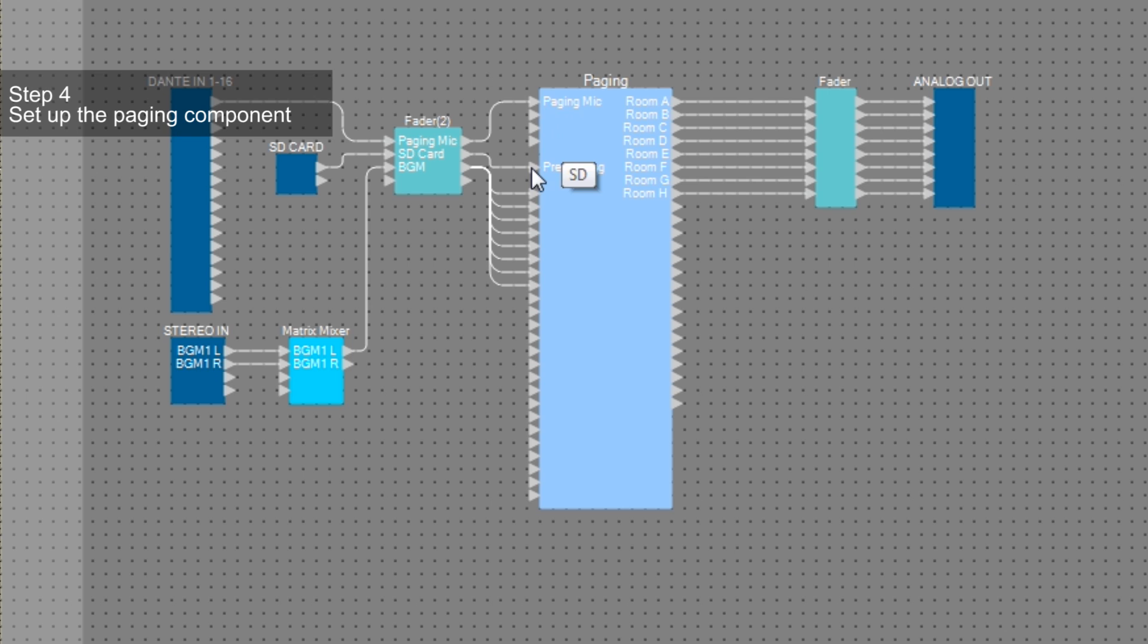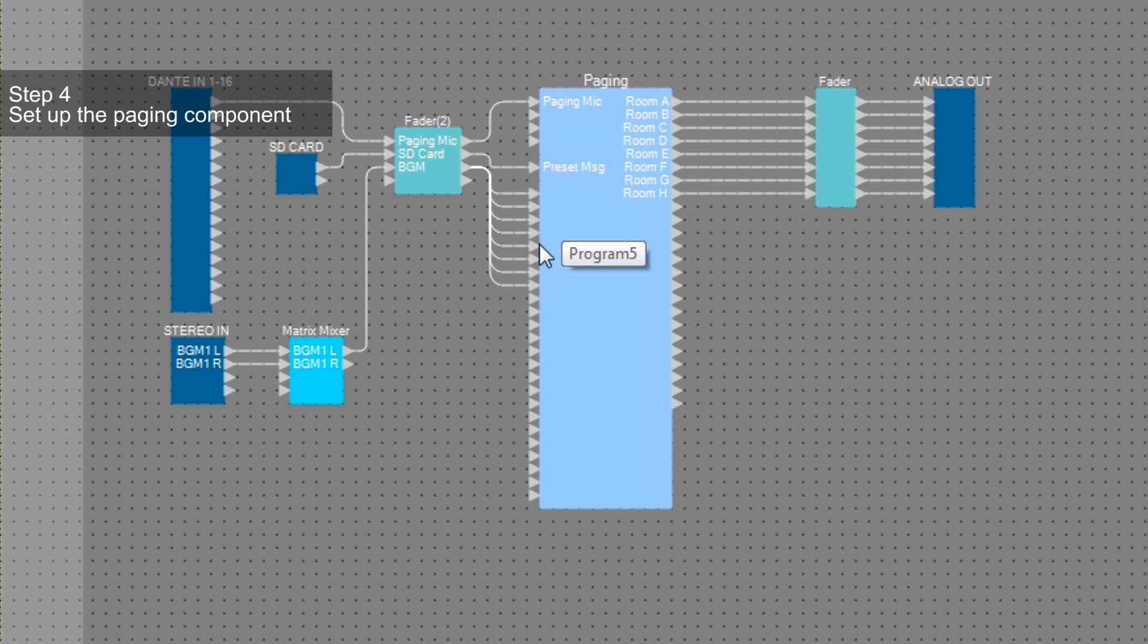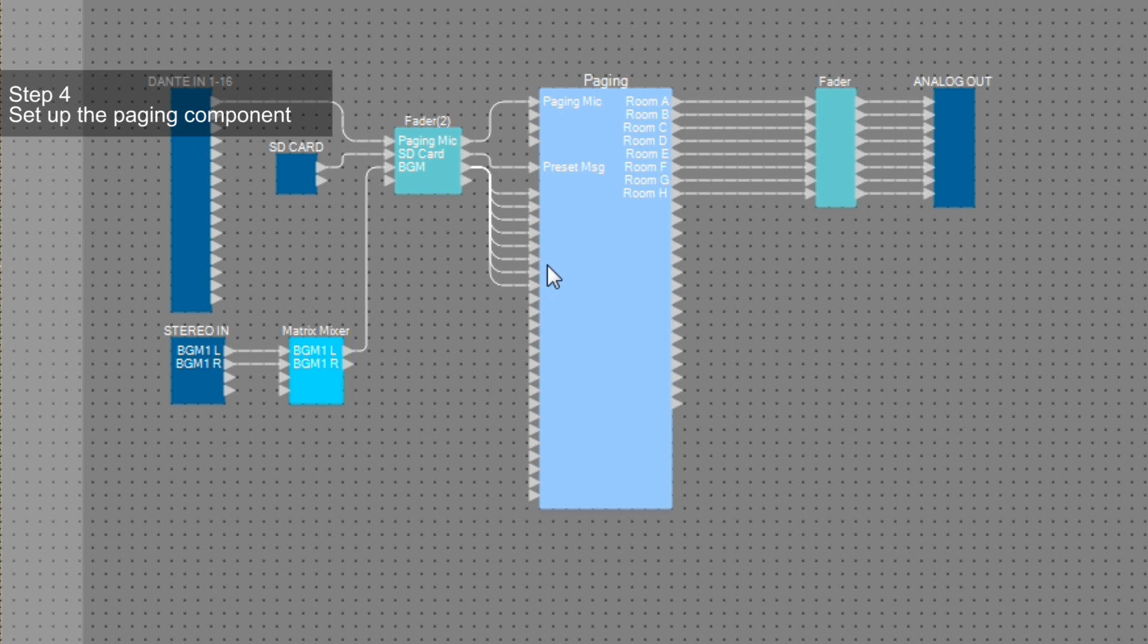Then, one SD input for programmed audio such as opening and closing chimes. There are 24 programs to input up to 24 different audio sources such as background music for different rooms. Each of the program inputs will be sent to different zones respectively. For example, PGM-1 to Zone-1 and so on.